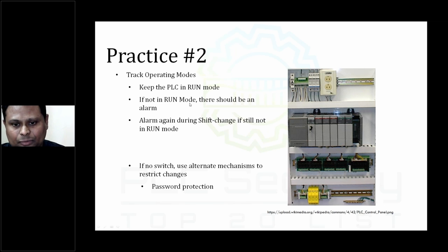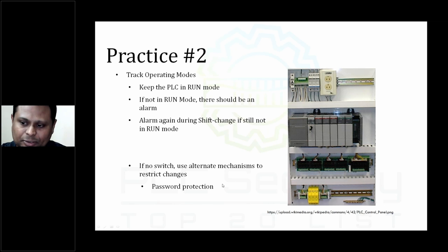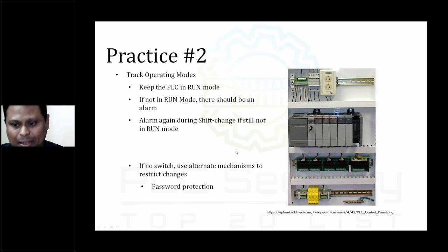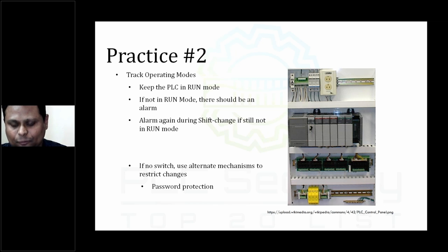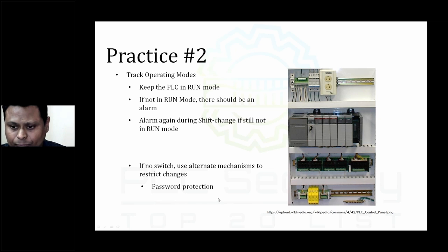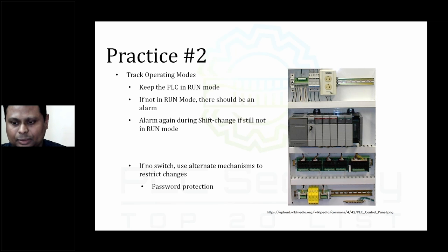We're trying to avoid the risk of someone over the network moving the PLC into Program mode and downloading code or causing a disturbance. The recommendation is to keep it in Run mode and always alarm on the HMI if it's not. For PLCs without a physical switch, you may need alternate mechanisms — like a password to prevent downloads — to track whether the PLC is in a mode that allows code to be written to the controller.